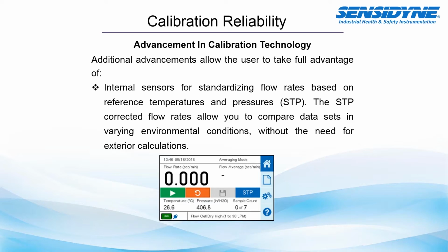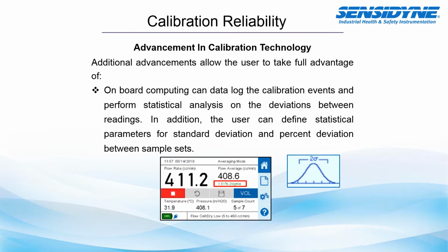Some additional advancements allow the user to take full advantage of internal sensors for standardizing flow rates based on those reference temperatures and pressures. As you saw earlier, there were some complex equations that were utilized. Well, some of the newer calibrators on the market will actually do those conversions for you to eliminate the calculation mistakes that could occur by doing this manually. Additionally, some onboard computing can data log the calibration events and perform statistical analysis on the deviations between the readings.